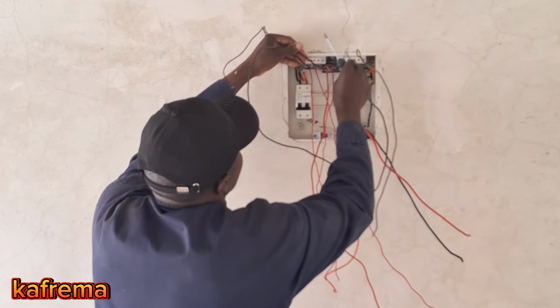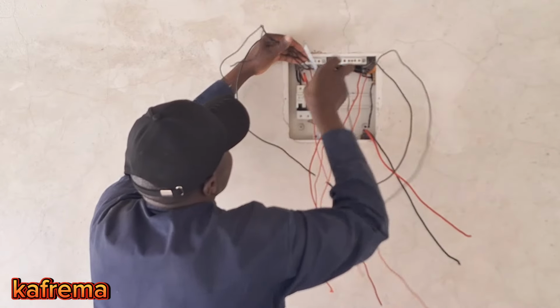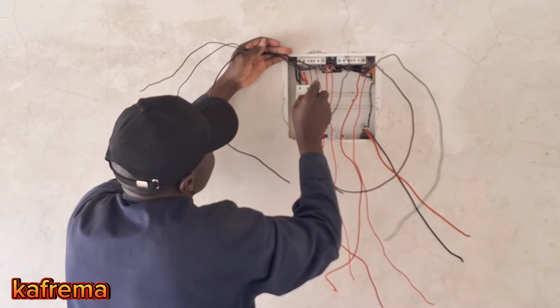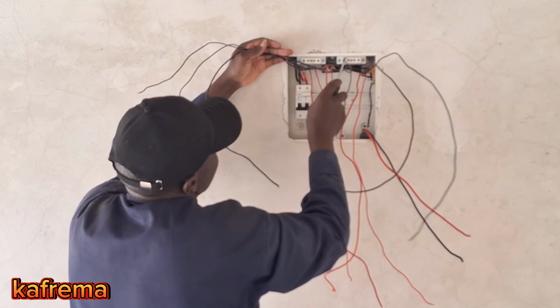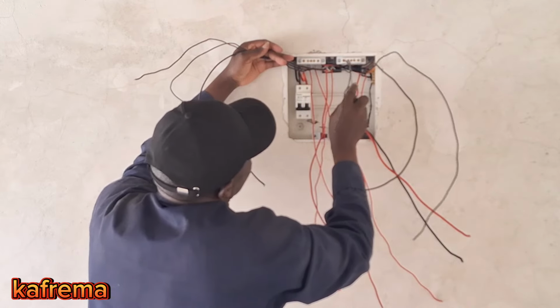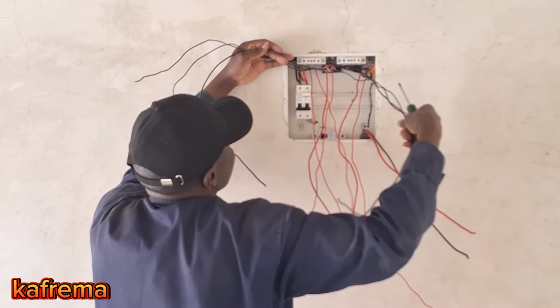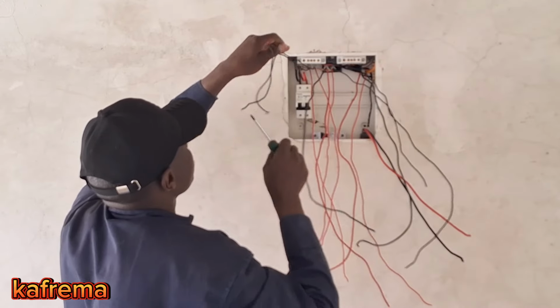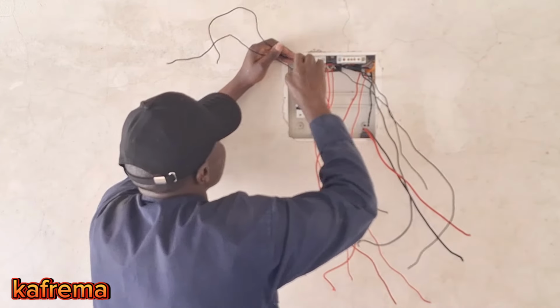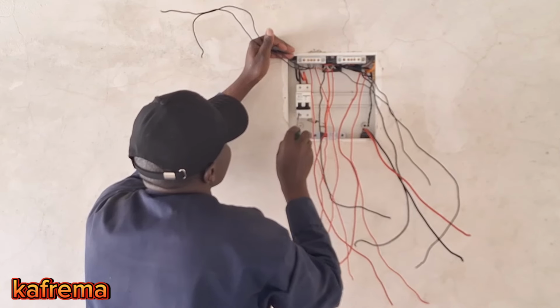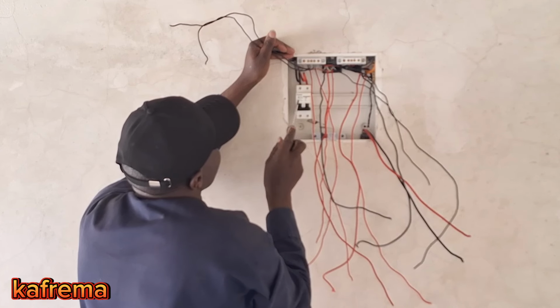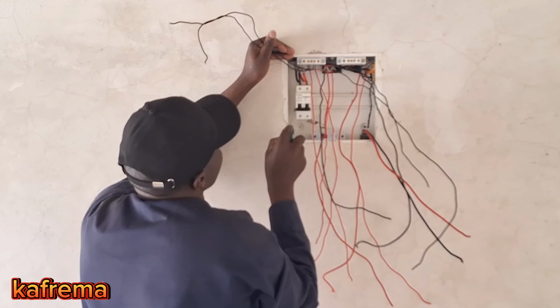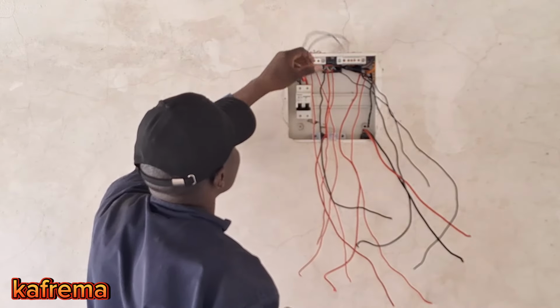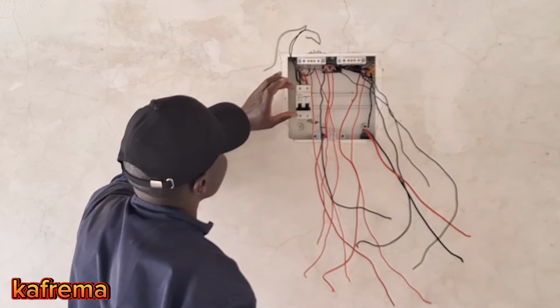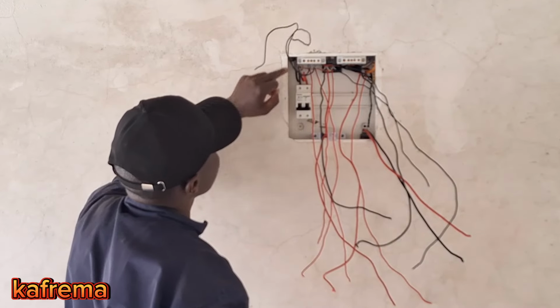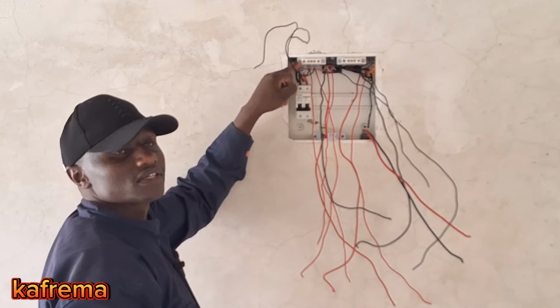So I'm going to do 3 here and 3 here. The last point and the first point I'm going to use as interconnection between the two neutral bars. So I'm going to use the 1, 2, 3 here for these 3 cables. Then the first will be used for the neutral from the main circuit breaker or the isolator. From this circuit breaker, it will go up to this neutral bar. This is the main isolator. From the isolator, the neutral will come to the first point here.